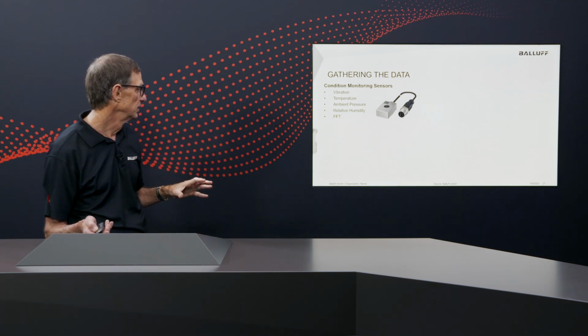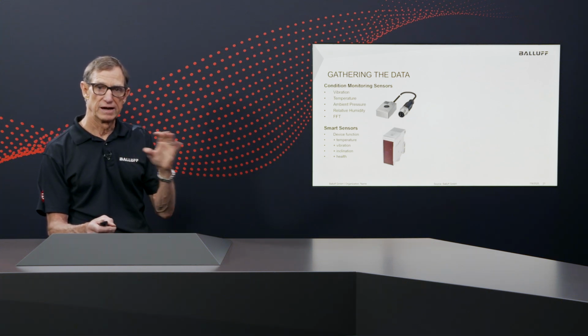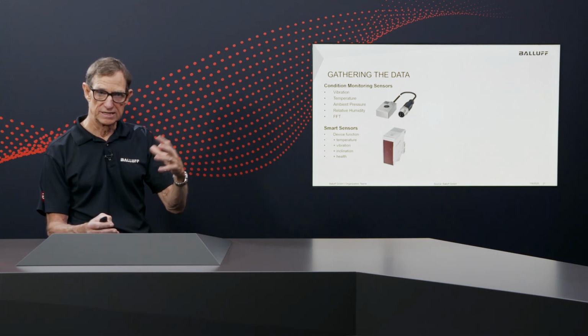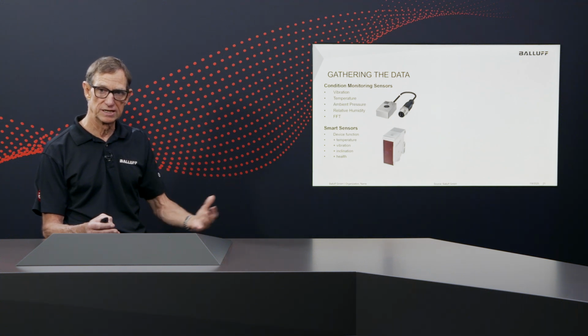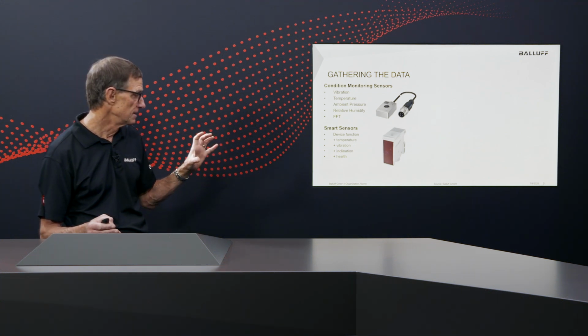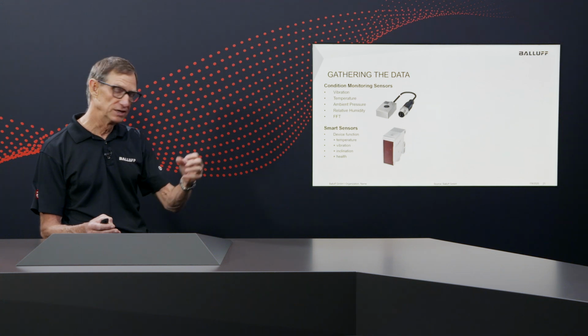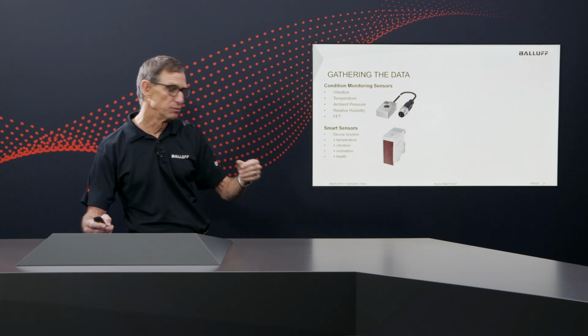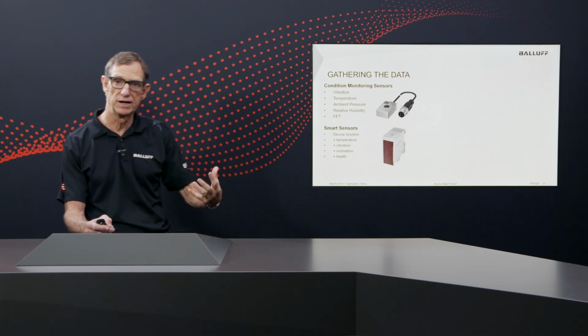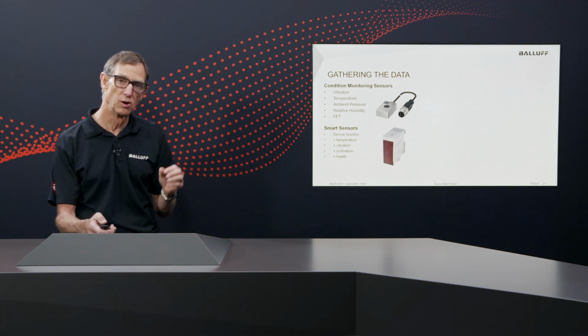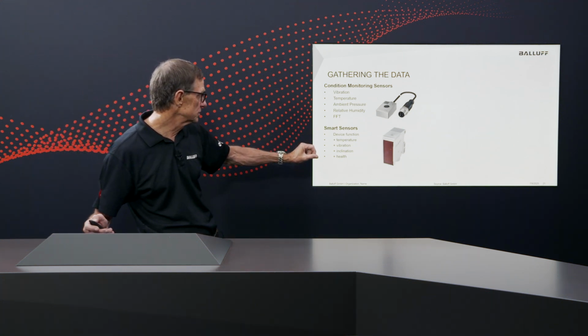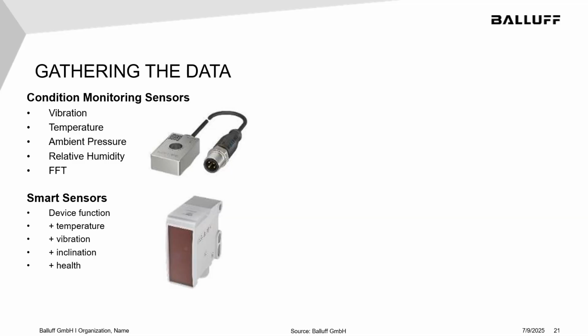There are smart sensors with a core function like photoelectric or inductive sensing, but with added capability to monitor temperature, vibration, inclination, and sensor health—a dual purpose sensor. It may not be as focused on condition monitoring data as a dedicated sensor, but it offers good enhanced capability where that data is needed alongside the sensor's standard function.